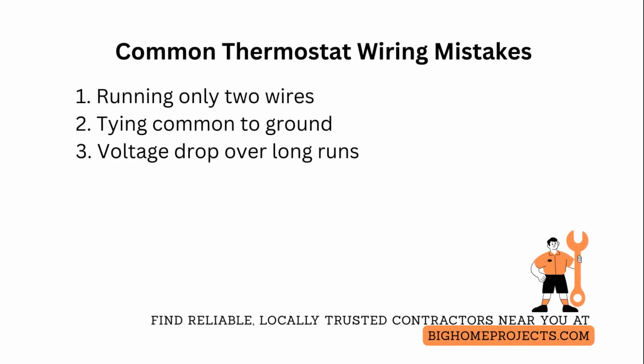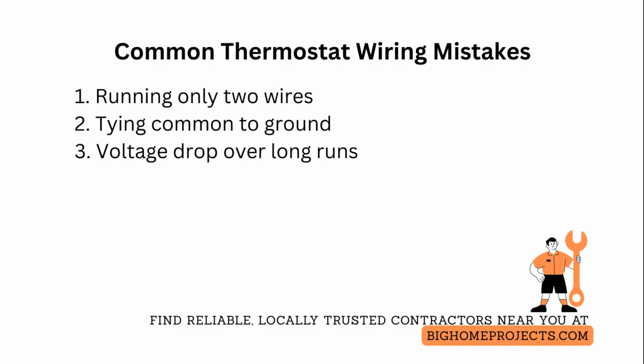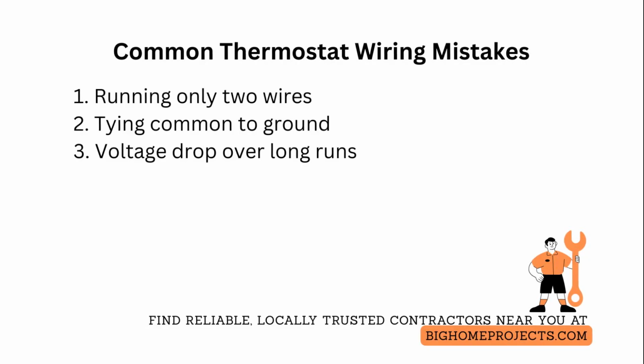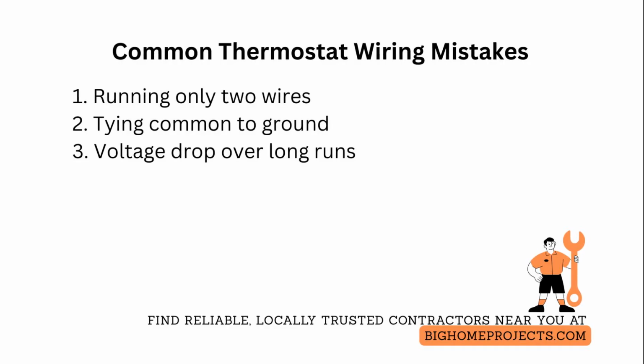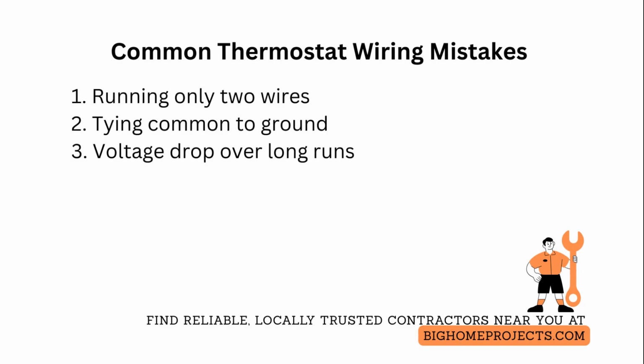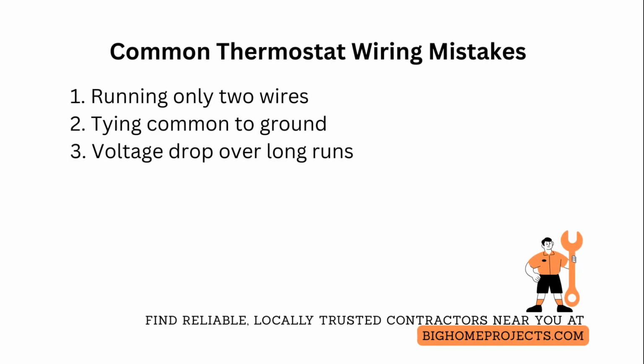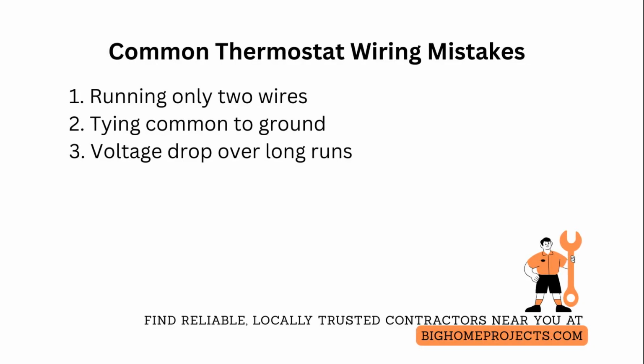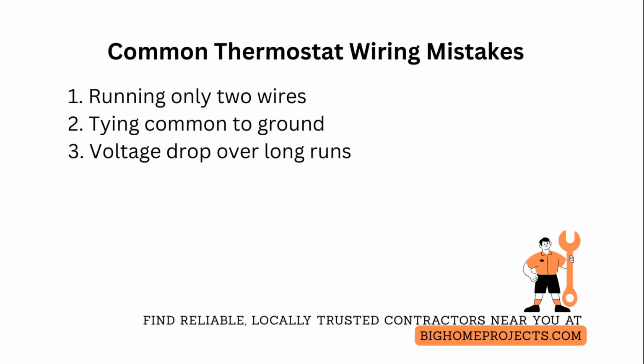One of the biggest issues is misidentifying the common terminal and tying a conductor to ground, which can damage transformers and controls. Fix it by testing for 24 volts and tracing the transformer's common terminal back to the control board before making connections. One of the frequent problems is voltage drop over long runs, causing intermittent thermostat behavior. Fix this by using a heavier gauge wire, reducing run length where possible, or installing a local relay or transformer at the zone to maintain proper control voltage.